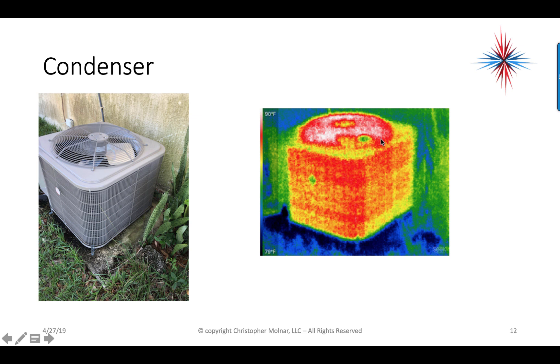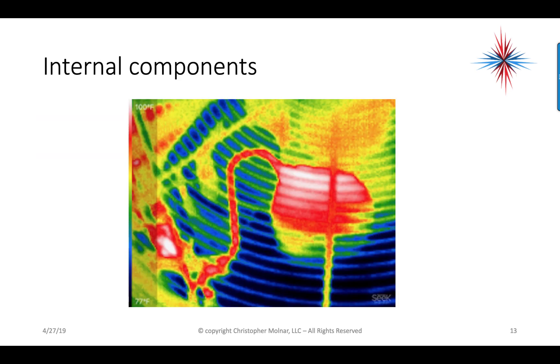Taking a closer look down through the running fan, I can now see the compressor and the reversing valve, and you can almost see the path of the refrigerant through this reversing valve, which is neat. You can check if a reversing valve is leaking internally, because you would have hot refrigerant all the way through. I'm seeing that perfect U shape in the reversing valve. If I had a leak anywhere in this system, where there should be reds I would be seeing dark blue and black.